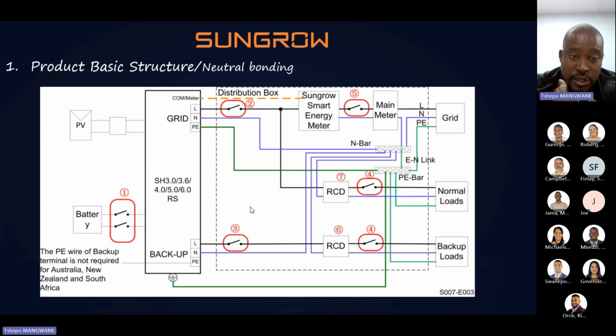Okay. Now I'll take you through. Please advise all the installers that buy the product from you that, according to the design for the South African market, the internal earth neutral bond relay inside the inverter is not enabled in South Africa. It is only enabled in Australia. So in this market, the installers have to bond the neutral externally just after the inverter. So neutral and earth have to be common with the grid. All right.